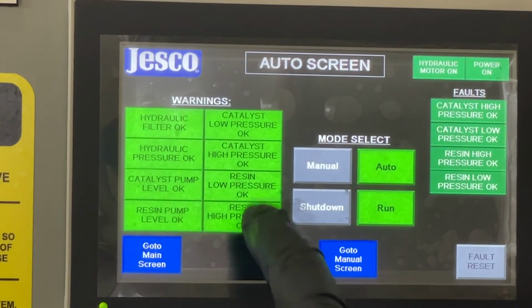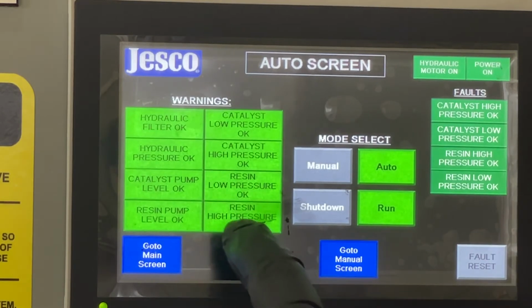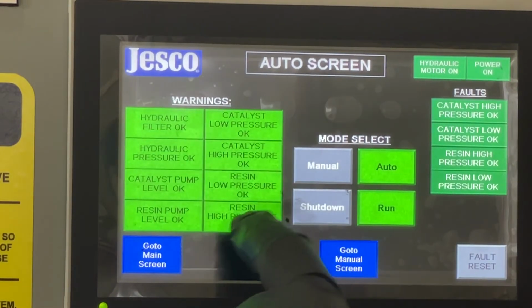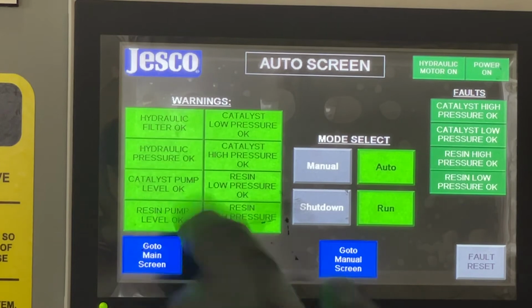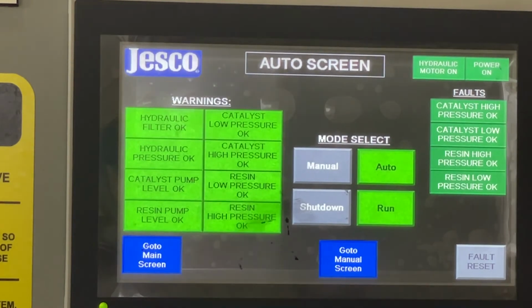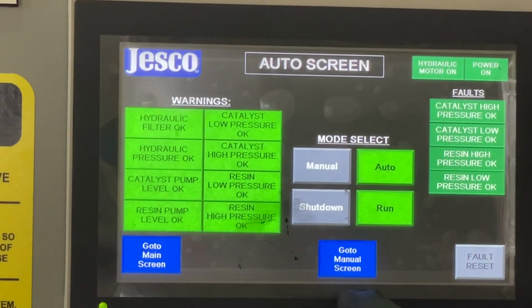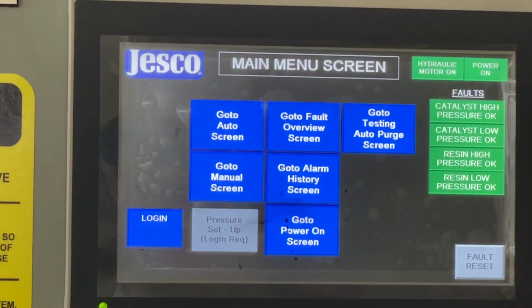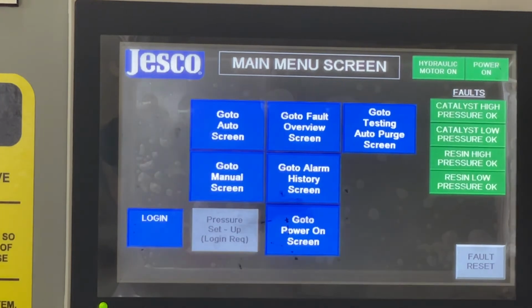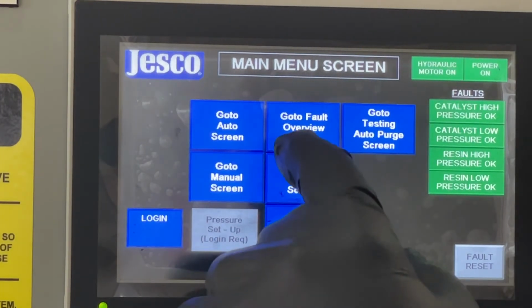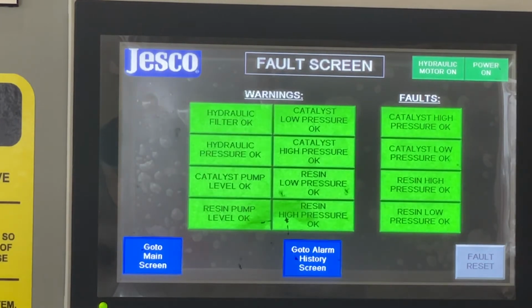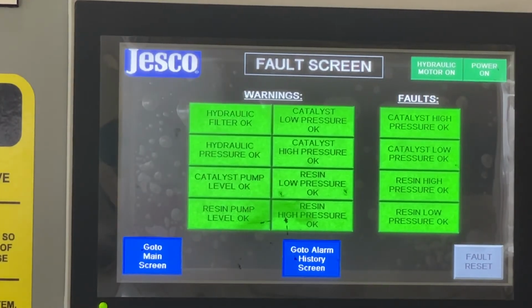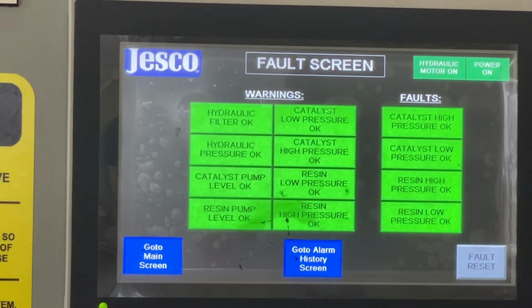Again, this shows any of your warnings. We have your pump low level warnings, your catalyst and resin pressures, and a hydraulic filter, which is just a warning indicator if your filter becomes dirty. We'll go back to the main screen. So we've gone over the manual, we've gone over the auto. There's a fault overview, which again just shows the current status of any of the warnings or fault situations. Right now everything's green, we're in a good condition.